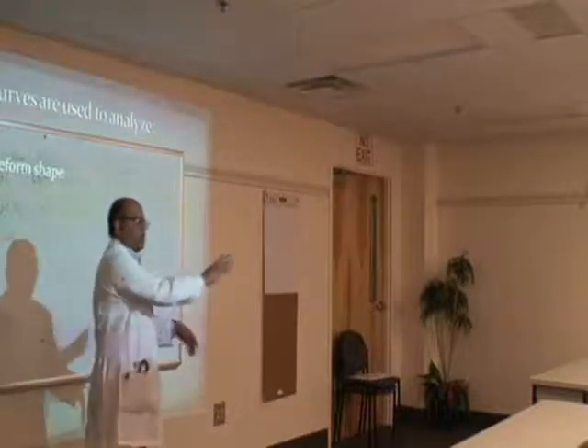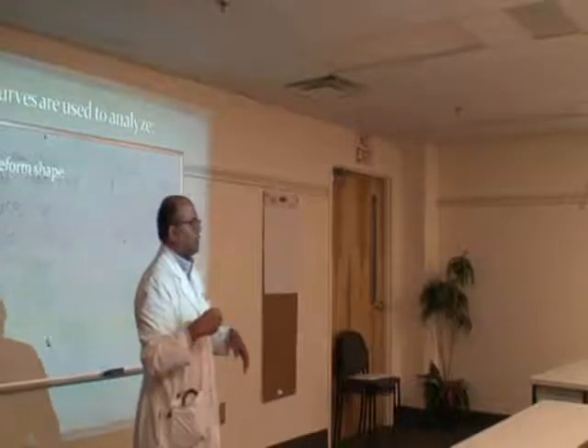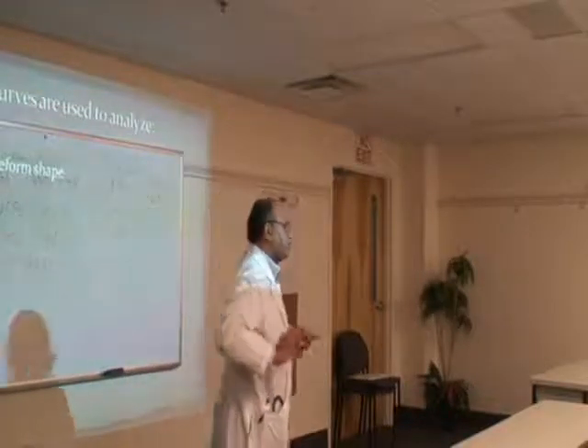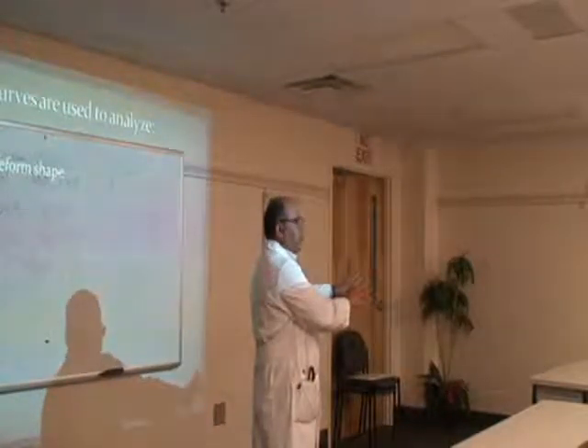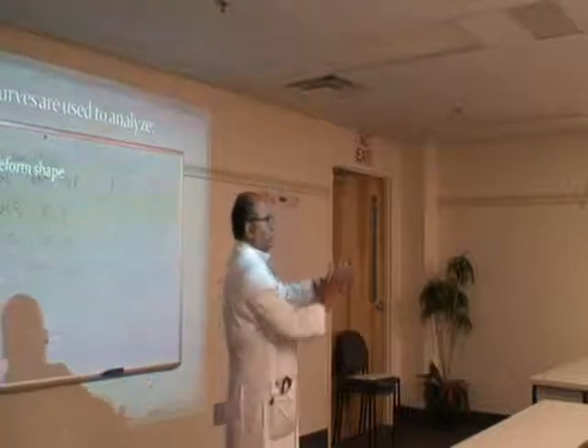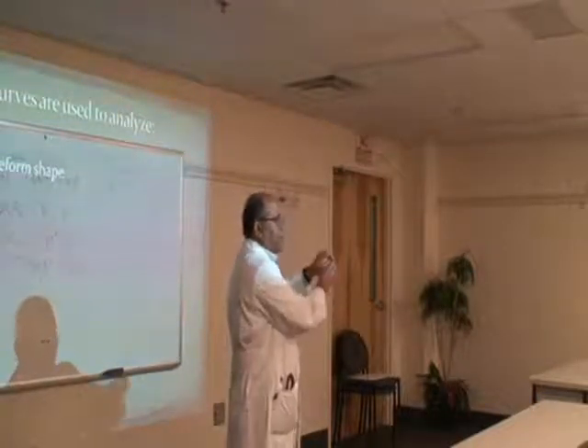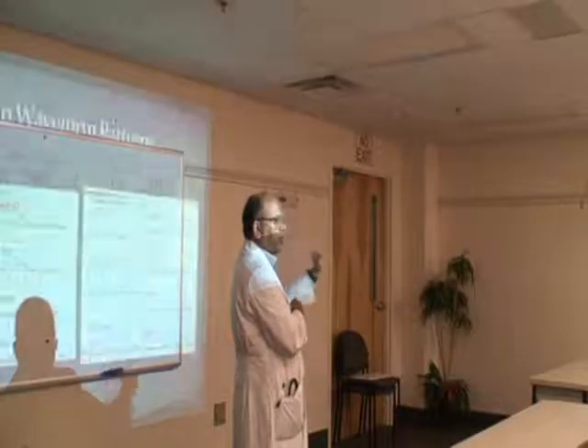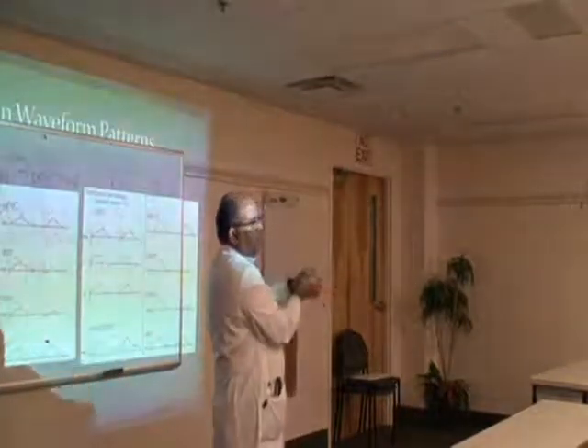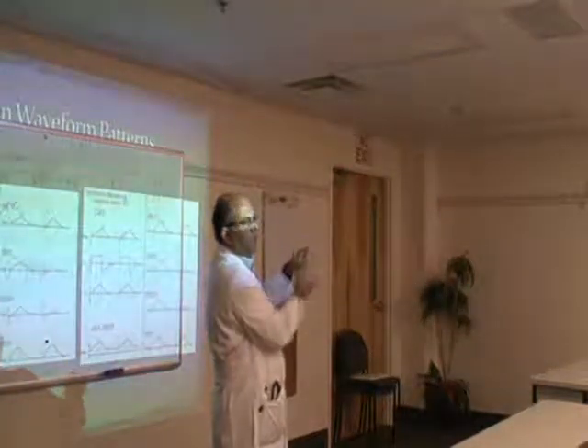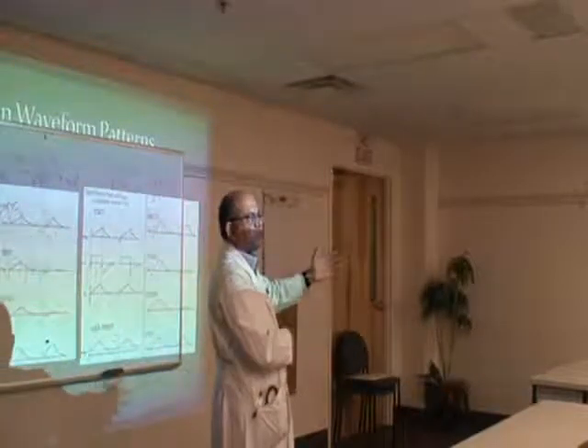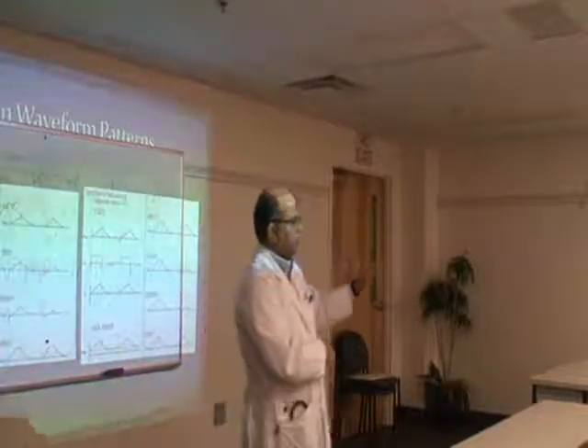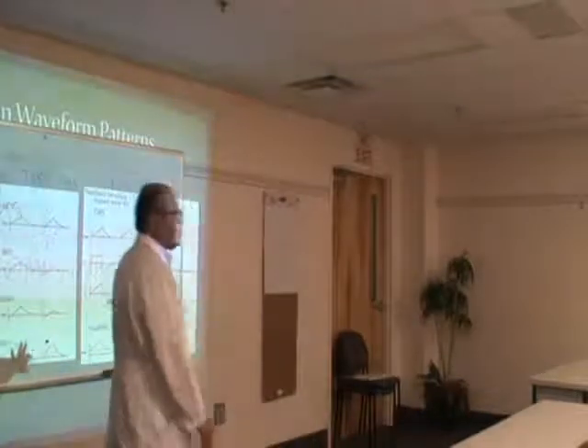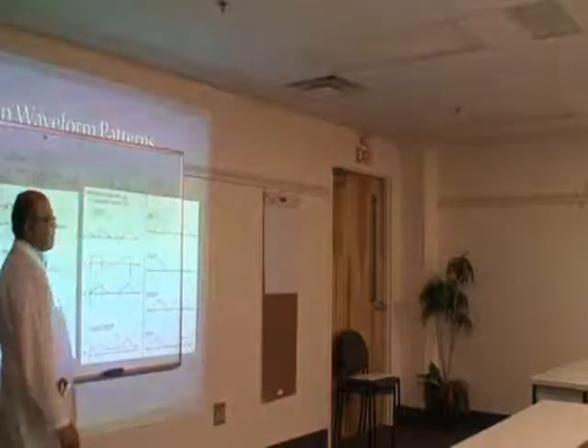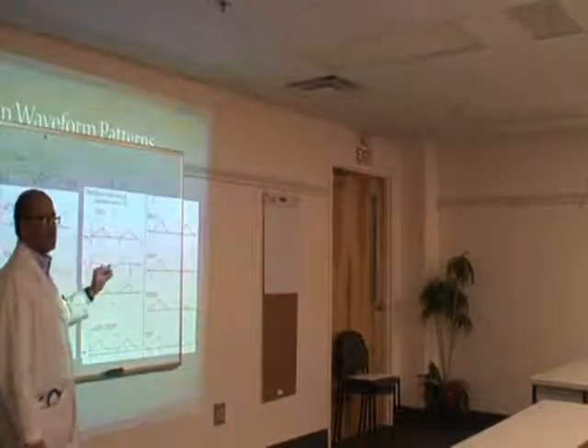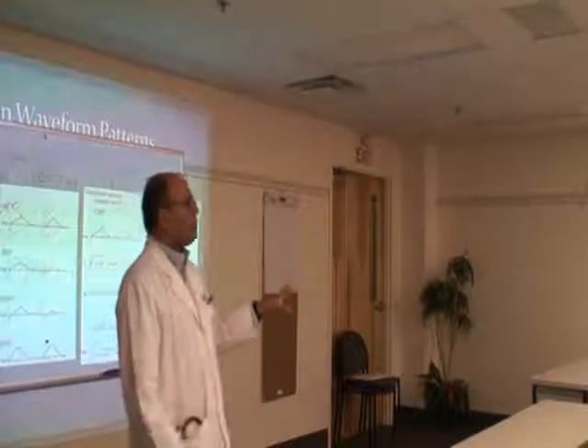One is pushing air in when the guy is breathing in at 14 centimeters. Say, hey, you're breathing in, let me give you extra help. Now you're breathing out. I'm going to back off from 14 centimeters and drop the pressure down to 8 to allow that CPAP or PEEP to kind of keep the airway open a little bit at the end, instead of dropping it to 0 where as he's breathing out the airway will close down. Okay, so CPAP is the PEEP at that end. Okay, questions or confusion? So that's BiPAP.